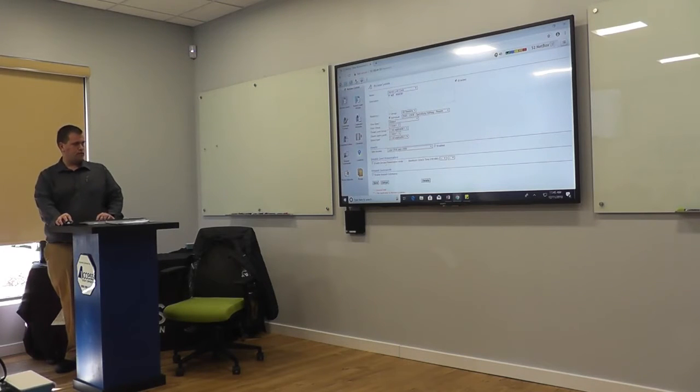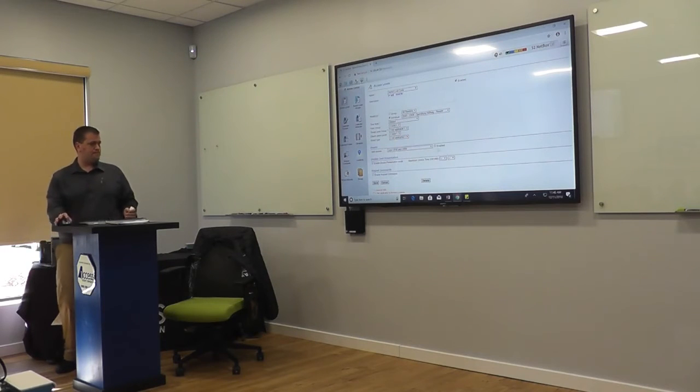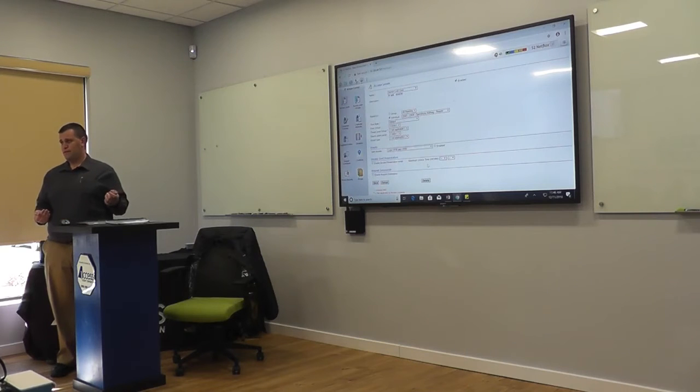So down here is the double card presentation. This is where you would assign that double card access to the access level. So it would get assigned to the access level, and then you could define a max unlock time if you wanted to. If there's not a time defined, then that reader's going to stay unlocked until you lock it. It's handy a lot of times where maybe you have rooms, conference rooms or classrooms, you want it to unlock for, the teacher comes in, they scan the door, unlock the door.